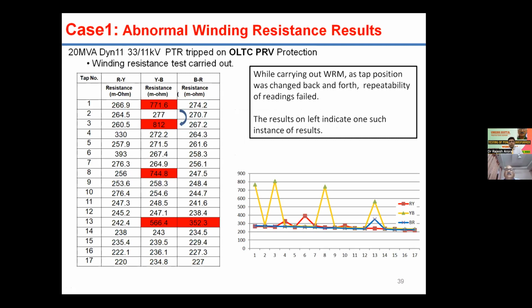Now, when we were testing the winding resistance of this transformer, as per the ideal condition, as per the design of the transformer, when I'm moving from tap number 1 to tap number 17, my winding resistance should decrease linearly. However, what we found was that at multiple tap positions, there was a sudden rise in the winding resistance. For example, take this case of the YB phase, which I am showing here. At tap number 2, I was getting 277 milliohms, and when I tested at tap number 3, it suddenly rose to 812 milliohms. Now we again retested at this particular tap only, tap number 3. The result was consistent, the same 812 milliohms.